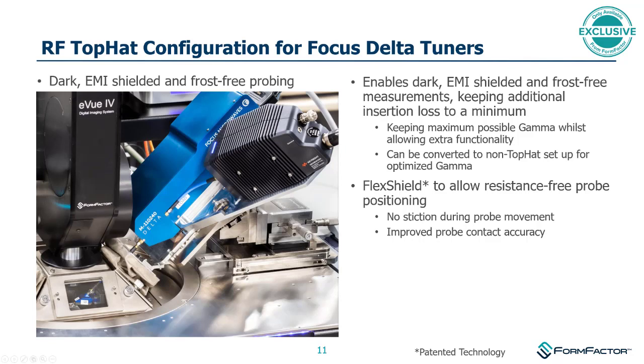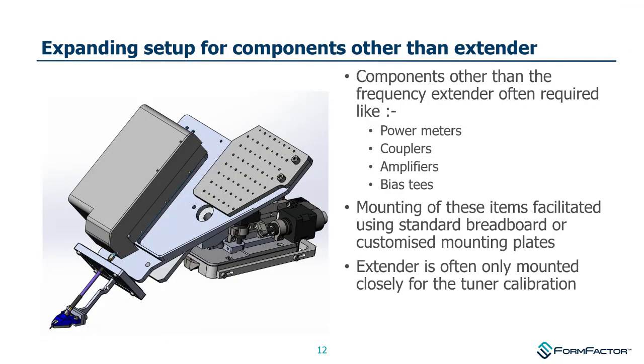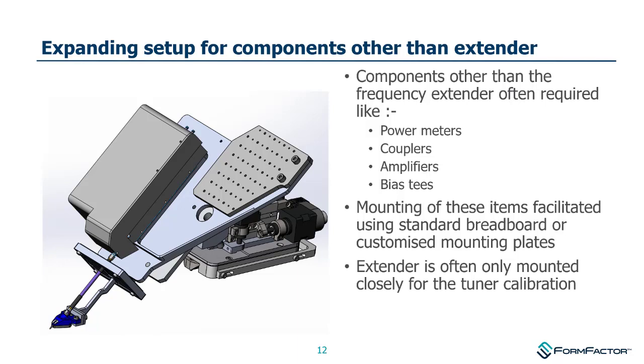We use a flex shield — a patented boot arrangement that is EMI-loaded, getting rid of external EMI with no stiction so you can move around easily with motorized positioners. The window provides excellent visibility of the probe tips and is coated with ITO to prevent buildup of static. We also have another cover plate that can instantly make it EMI-shielded and dark. We realize that you won't always have a frequency extender attached — most setups will involve other instrumentation such as power meters, couplers, amplifiers, and bias T's. For this we provide a breadboard plate with mounting points for custom breadboard plates to make the setup more complex.